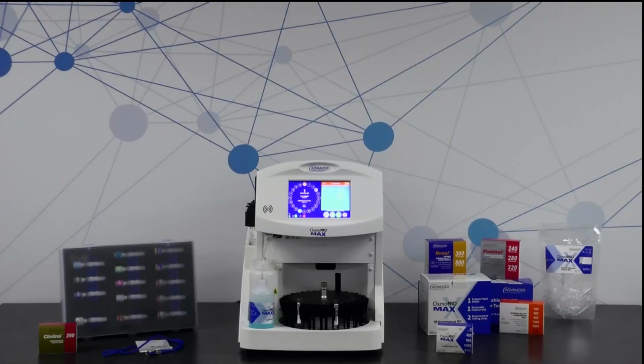What would happen if somebody accidentally ran a sample with the cap still on? The probe is always sensing, looking for a liquid level. When it bumps into something hard, it'll throw an error, and it won't be a fatal error. It will actually just tell you, hey, I bumped into something. We have a probe crash error. We're just going to move on to the next sample. Is that okay? And then you just hit yes, and it'll move on to the next one.